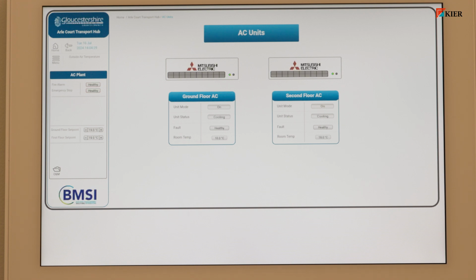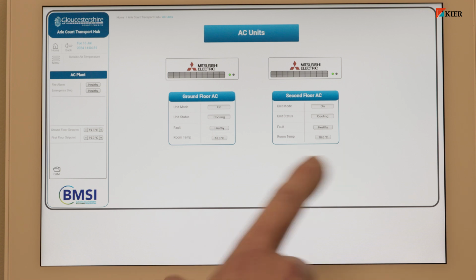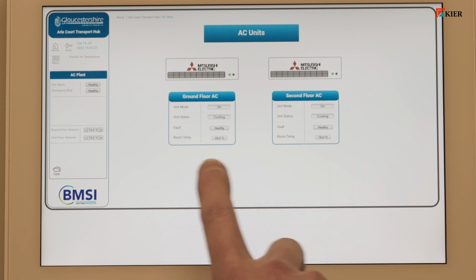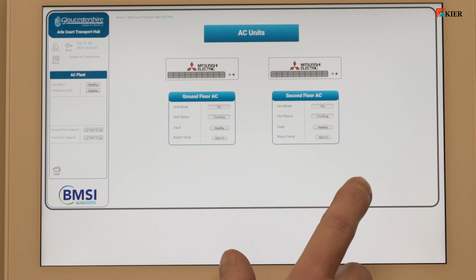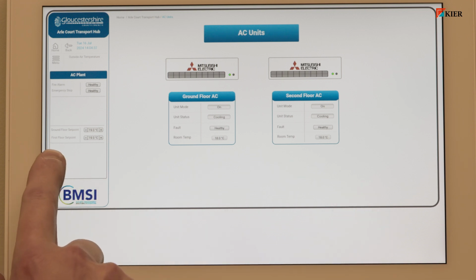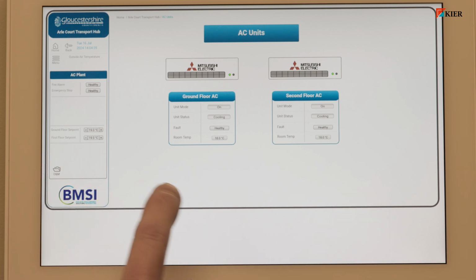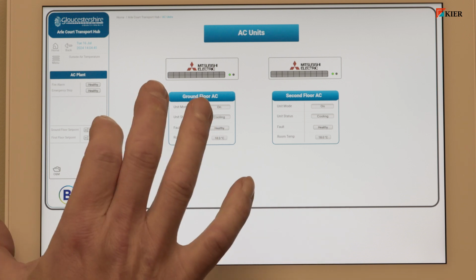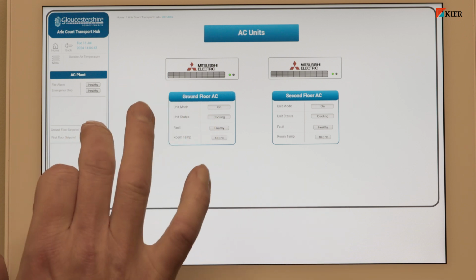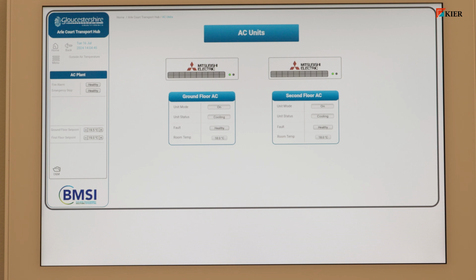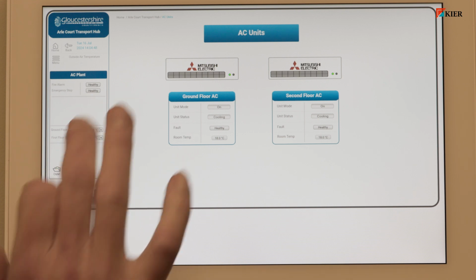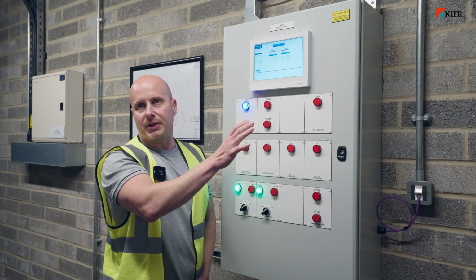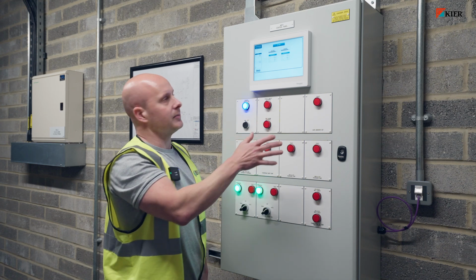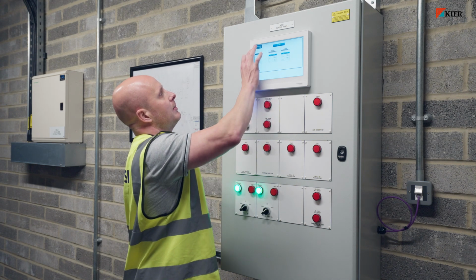Again, just a very quick overview. It tells you, is the unit on, what it's doing, is it in fault, and what the temperatures are. What you've also got on this side here is set points. So if you wanted to change the temperatures on these, you could just very briefly tap in that button there, and you can see it's increased. But as these are comms rooms, generally you would just leave them as they are. Okay, they're normally set at 19 degrees. Okay, go back to the main page once again.